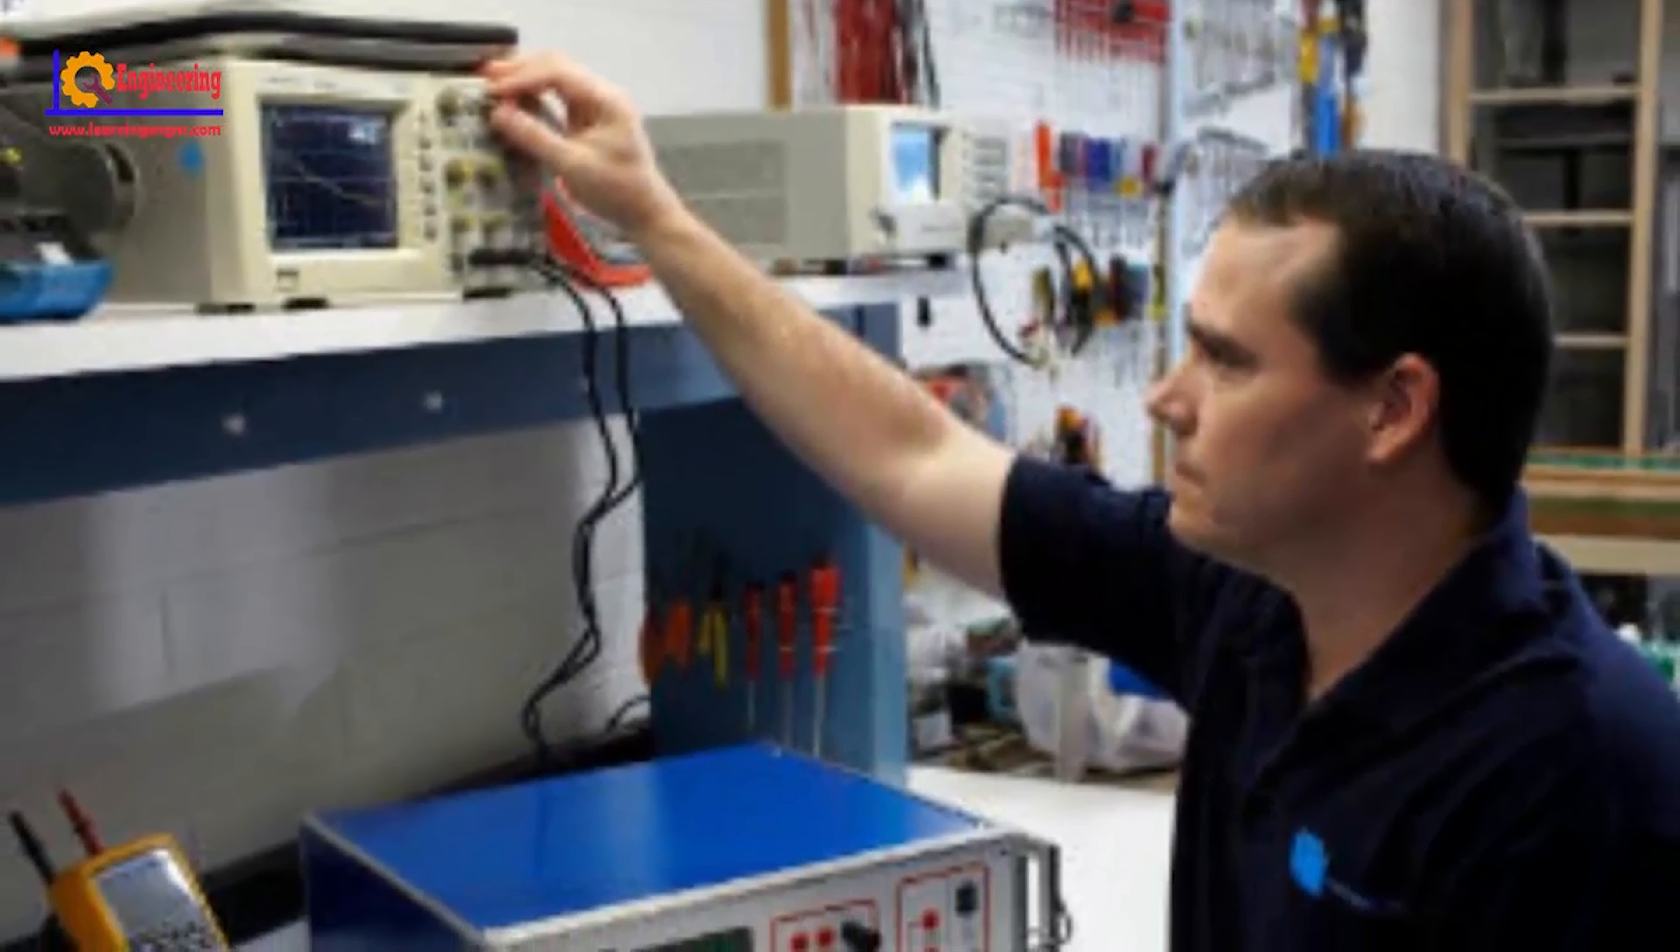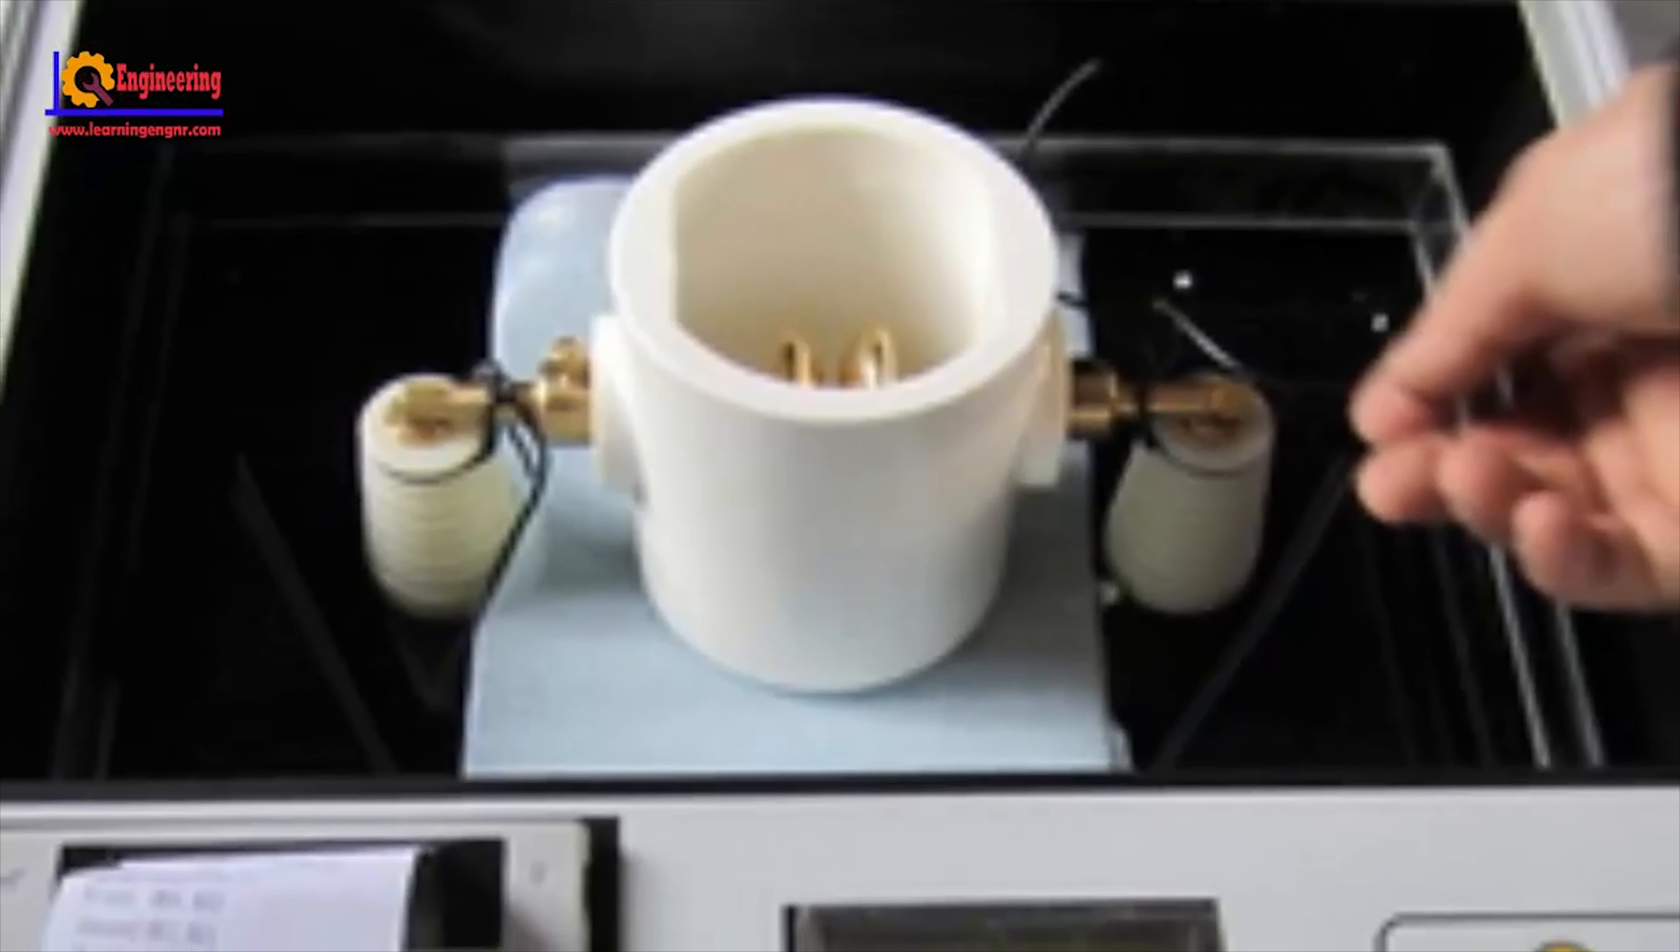stressed to a greater extent than under normal operating conditions, should not be breached for the product to pass. In most cases, the device is stressed to twice its normal operating voltage.